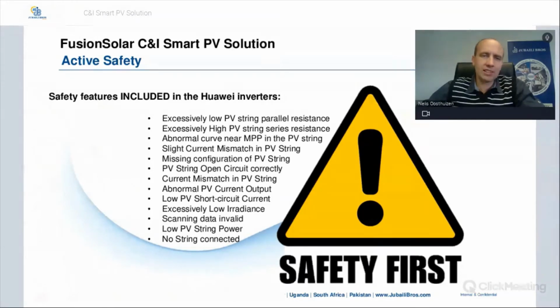Some of the active safety features built into the inverters are: excessive low PV string parallel resistance, excessive high PV string series resistance, abnormal curve near MPP in the PV string, slight current mismatch, missing configuration of the PV string, open circuit, current mismatch, abnormal PV current output, low PV short circuit current, excessive low irradiance, scanning data invalid, low PV string power, or no string connected.